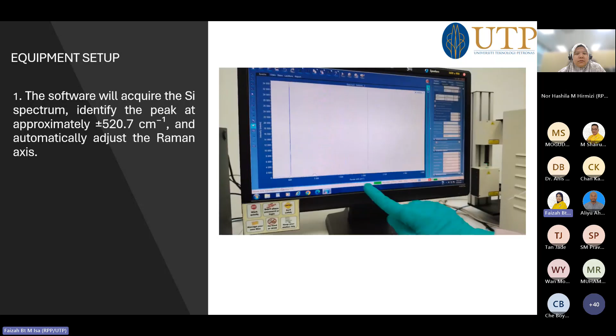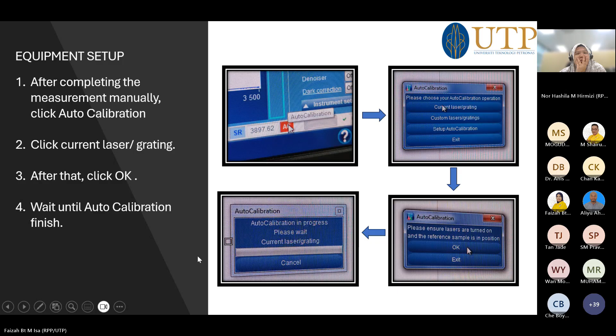Actually, before this, I showed the manual setup for calibration. After completing the measurement manually, we must do the auto calibration. This is the picture, I show you the step by step auto calibration. Just click the auto calibration and then click current laser grating. After that, we click OK and then wait until the auto calibration finishes.